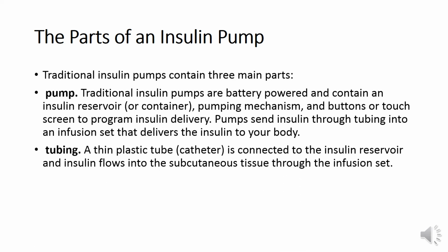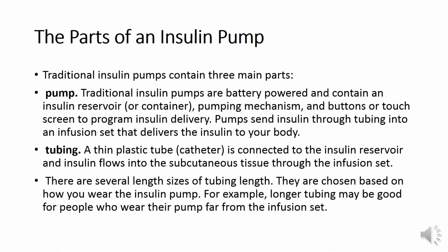Then the tubing. A thin plastic tube is connected to the insulin reservoir, and insulin flows through the infusion set into the patient's tissue. We can use several tubing techniques, which mainly depend on how the insulin pump is worn.